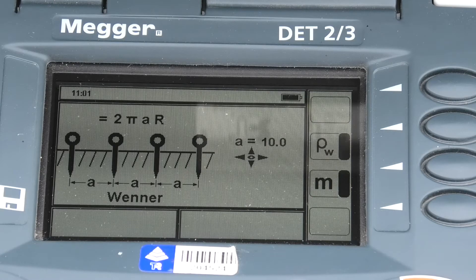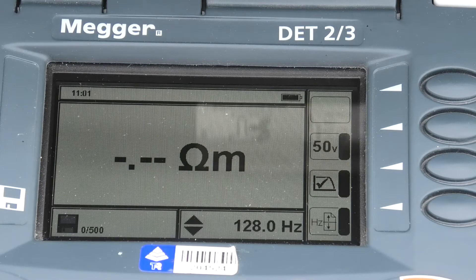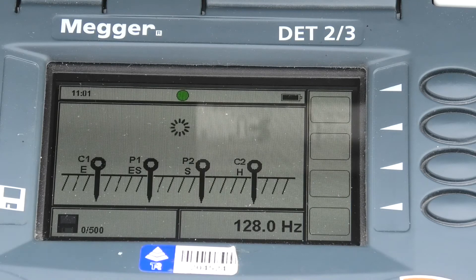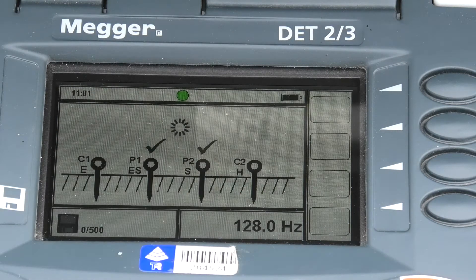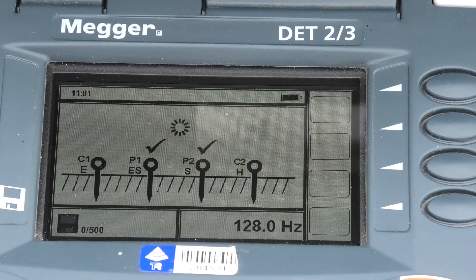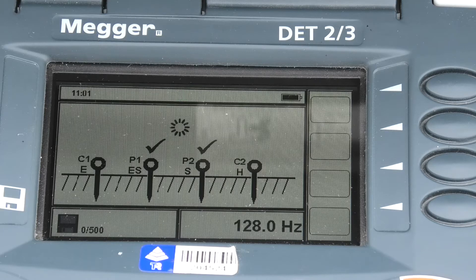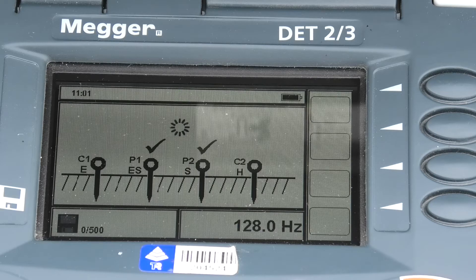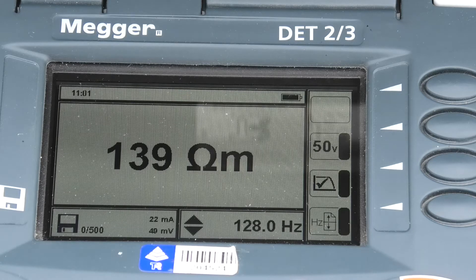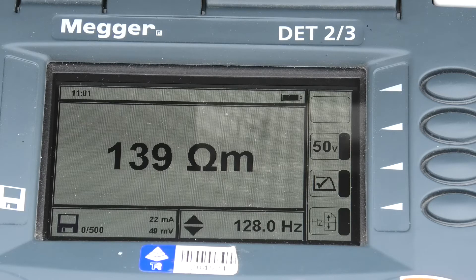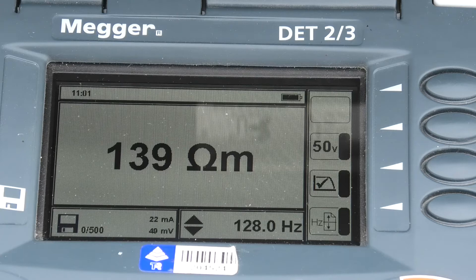Now it's simply a matter of OK, and then hit test. And it checks that everything's set up correctly there. And there, 139 ohm metres. There's my soil resistivity at this point. Now this will change with moisture content of the soil, electrolytes in the soil, all sorts of things.